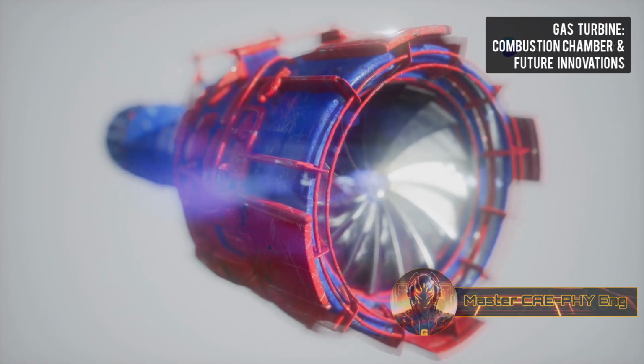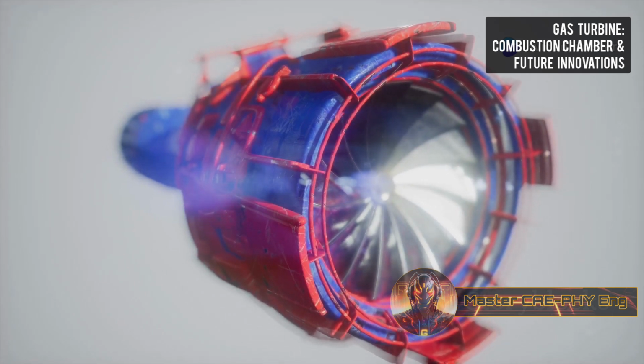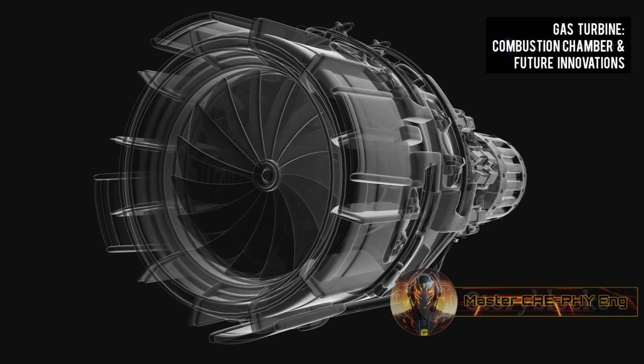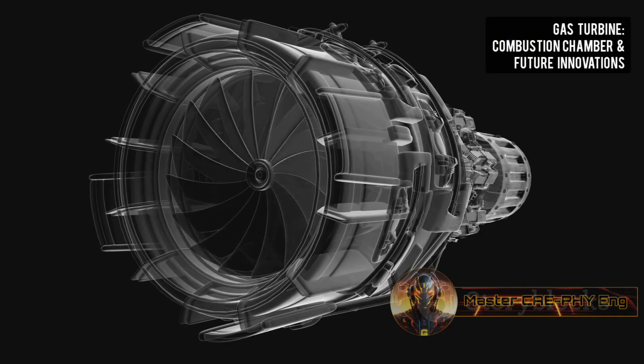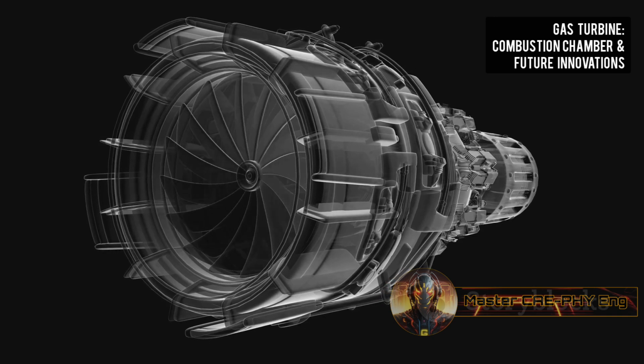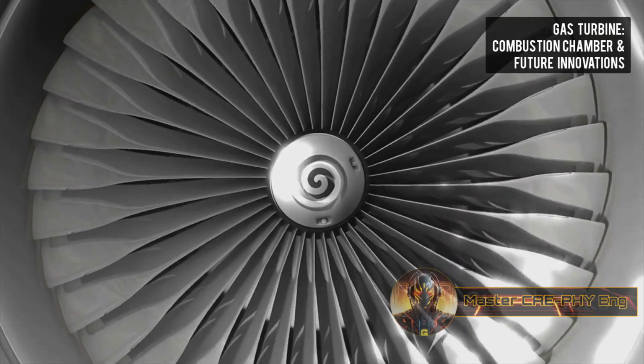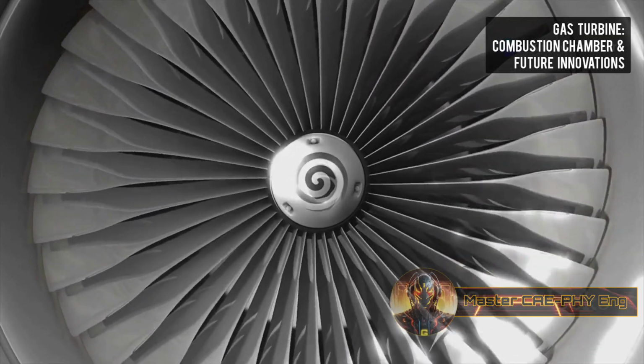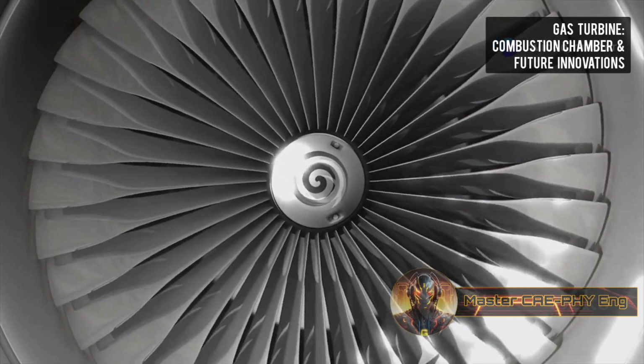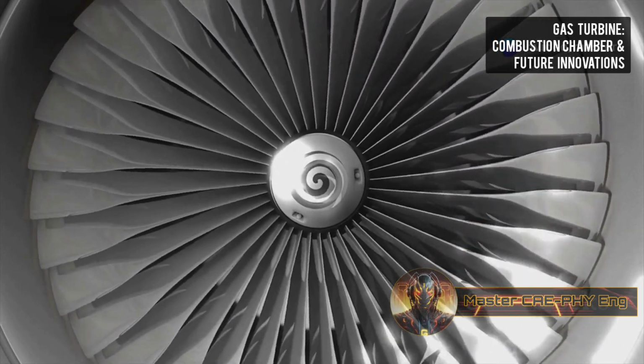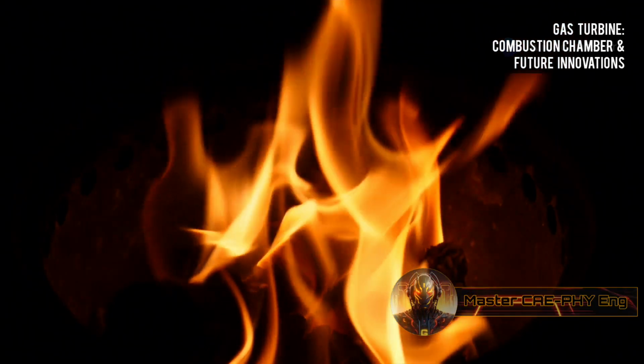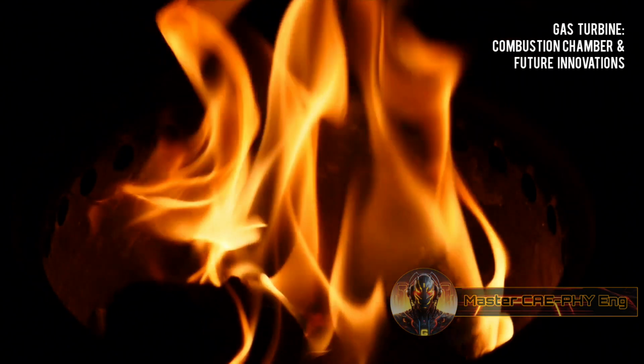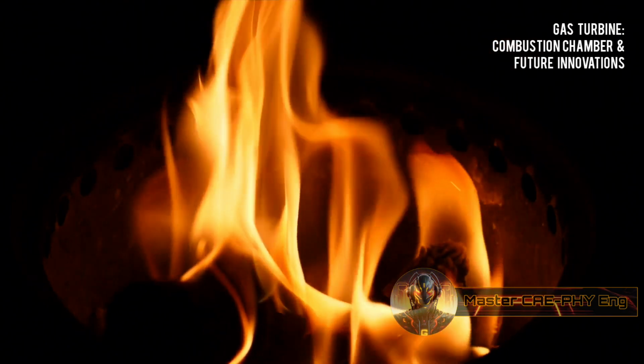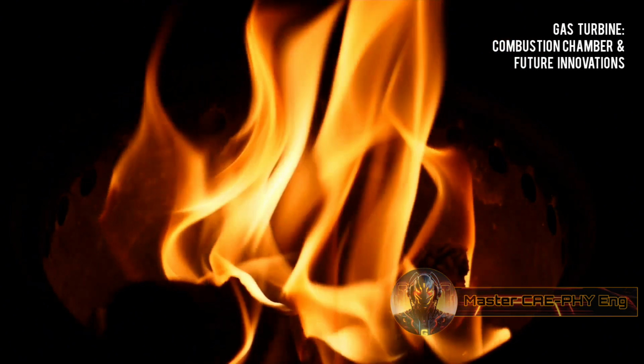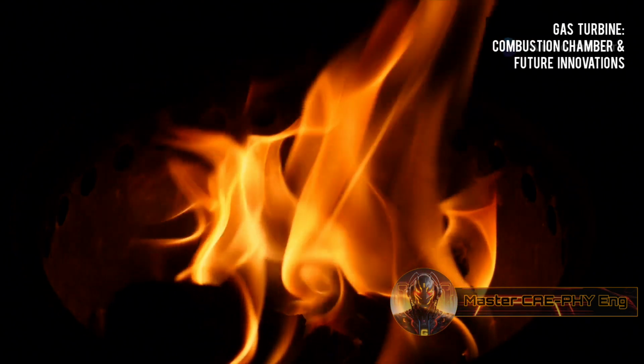Swirlers are crucial components within the burner assembly. They impart a rotational motion or swirl to the incoming airflow before it mixes with the fuel. This swirling motion creates a complex aerodynamic field characterized by a central toroidal recirculation zone. The recirculation of hot gases provides a continuous source of ignition for the incoming fresh fuel-air mixture, thereby anchoring and stabilizing the flame.